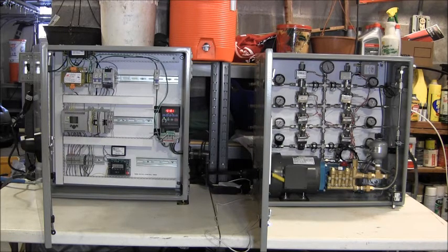You can see the one here on the left takes all the wires from this terminal block here. There are actually 28 wires here off these terminal blocks. Some of them are ganged together a little bit for grounding and for neutrals. But all those wires go into that 12-foot cable assembly over here. And then you can't see it, but there's another terminal block in the back that feeds power to the solenoid valves, and then feeds power to each one of the controllers or the transmitters that monitor the unit. One thing I didn't point out, each unit does have a gauge on it. So we've got solenoid 1, 2, and 3 open right now, but we only have water coming out of number 2. You can see that right now it's running at just about 200 psi. And then we've got a main gauge also up here. So each one has its own gauge, and then we have a main gauge.